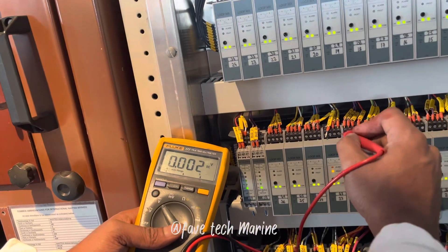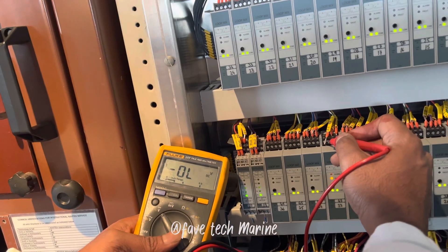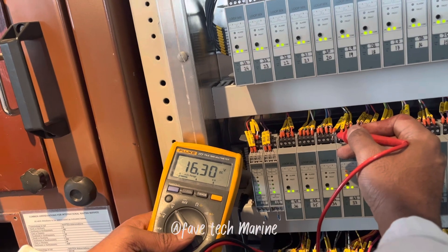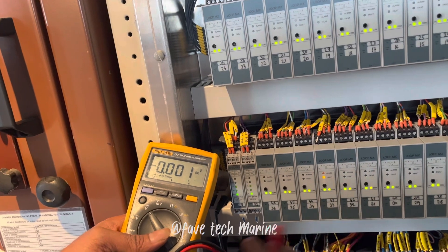After fixing the cable, let's go measure at our control panel. As you can see, the return voltage is good. We've cleared our fault, so we're going to connect the cable back and then reset the alarm.